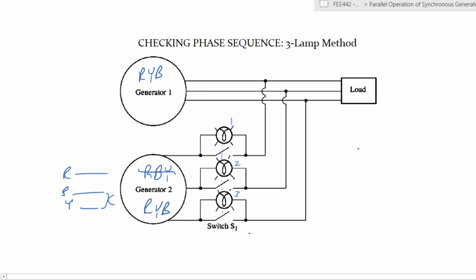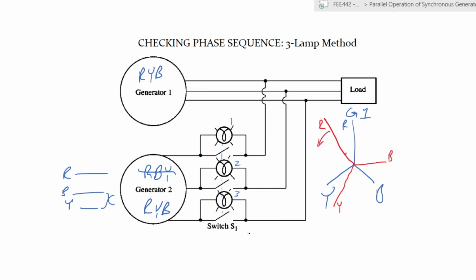Now the lighting up and dimming is not due to the peaks and troughs of the sequence itself. It is because if we take, for example, the phasors of the system, generator 1, which are red, yellow, and blue, your generator 2 would be similar, because they are connected 120 degrees apart from each other. So R, Y, and B. We've already assumed they're in the same phase sequence, so they match each other in terms of the phases. If you were to superimpose the phasors of each, assuming 120 degrees all across, the phase angle of generator 2 may be slightly faster or slightly slower than the existing generator 1 phase angle.